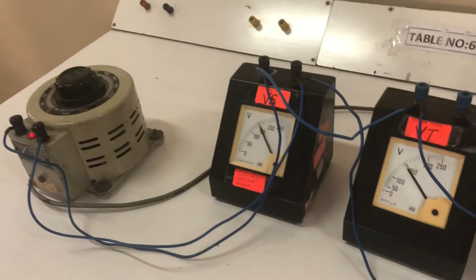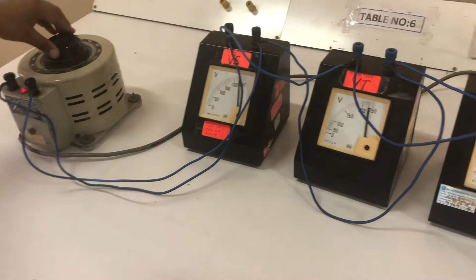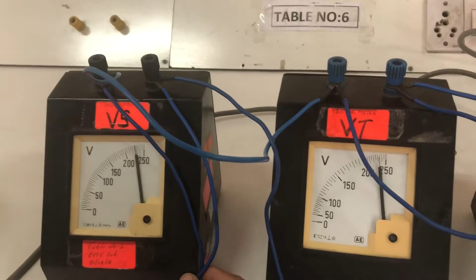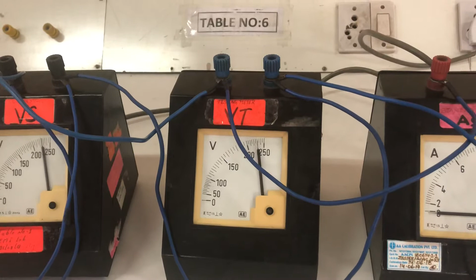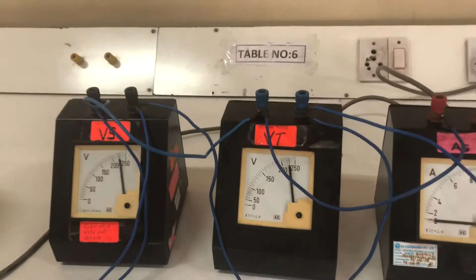Now the last reading we are fixing to 230 volts. The voltage for a single phase maximum we can give is up to 230, so we are fixing it to 230. Here we are having 230, and in the test it is just deflecting - not 230, it might be bit more, 232. So like this you can calculate the error in the voltmeter.